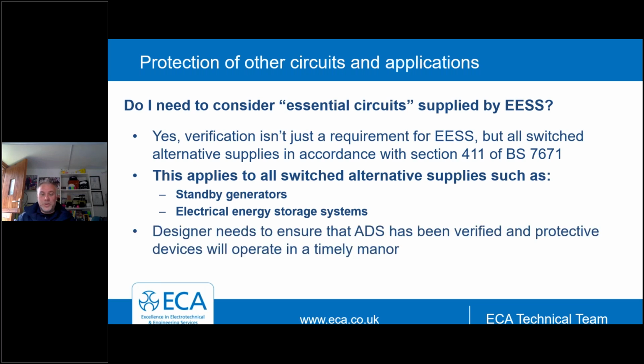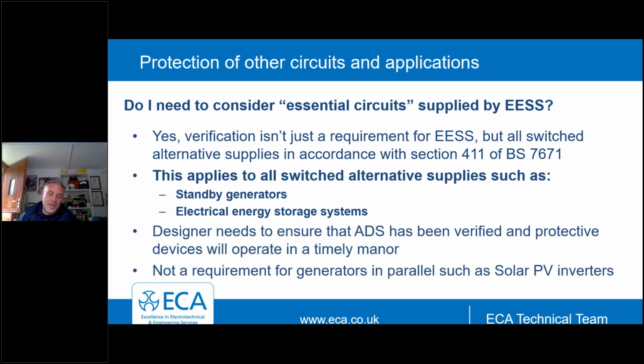Do we need to consider what we call essential circuits? Loss of main circuits. This has many different forms. Emergency power circuits, some people call them. I know them as essential from sort of data center history, but other people will call these different things. Do we need to consider what we're doing, for example, when we're running off an alternative supply, a switched alternative supply? So not when we've got solar PV, because that's in parallel, but when we're running off diesel generators, other types of generators, battery storage. Do we need to make sure that our circuit protection works?